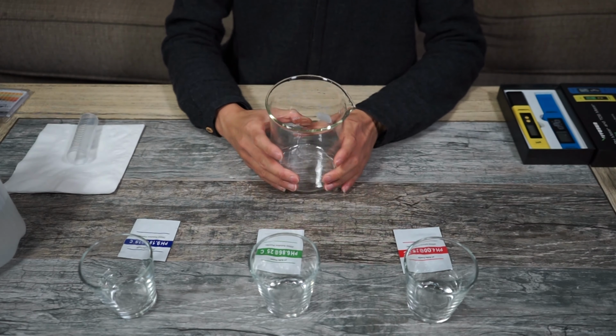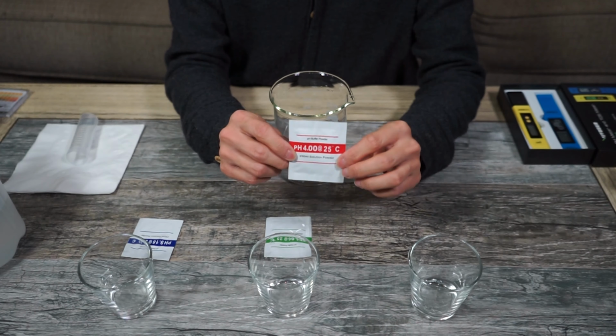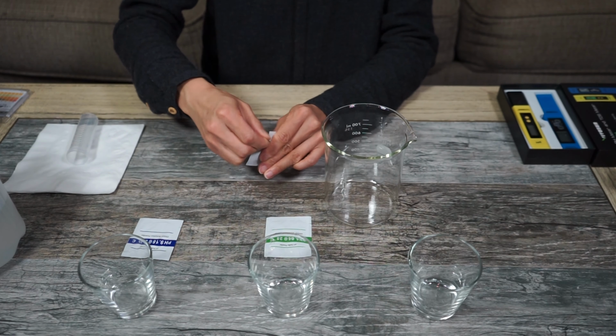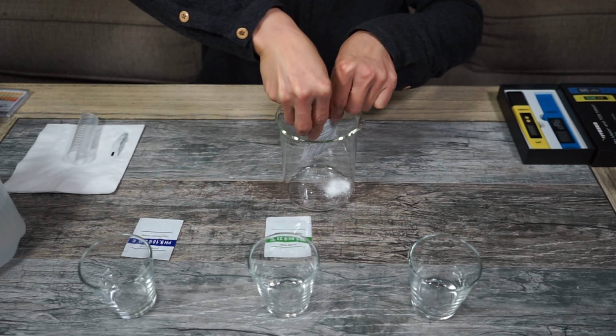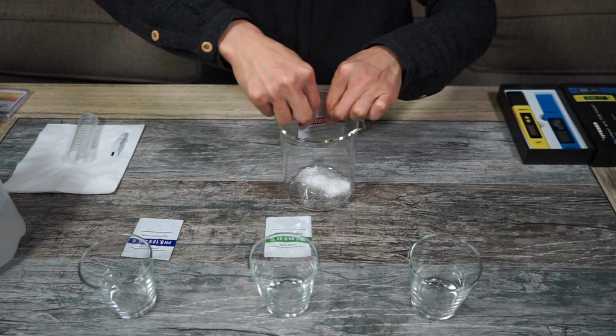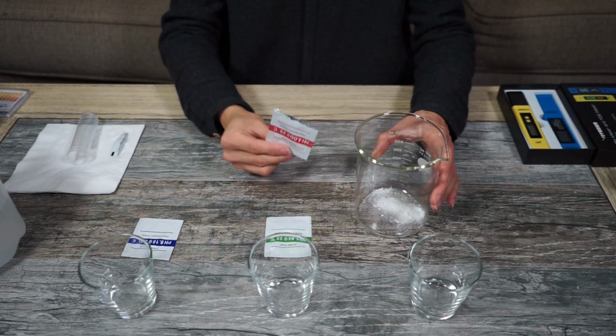The pH meter was shipped with 3 bags of powdered buffer for calibration. Before starting, we need to prepare distilled water. Distilled water is very pure water and basically does not contain any impurities. Distilled water can be purchased from supermarkets. We also need 3 glasses, which should be cleaned and rinsed 3 or 4 times with distilled water to ensure that the glasses do not contain any residue. My glass is a bit small here, so I start by using a large clean beaker to mix up the solution.